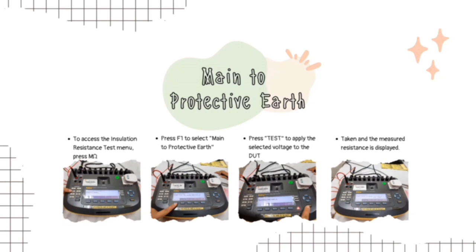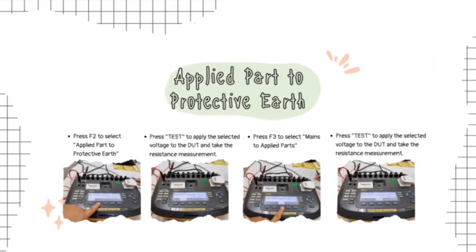Take and the measured resistance is displayed. Next is applied part to protective earth. First, press F2 to select applied part to protective earth. Then, press test to apply the selected voltage to the DUT and take the resistance measurement. And then, press F3 to select mains to applied parts. Then, press test to apply the selected voltage to the DUT and take the resistance measurement.